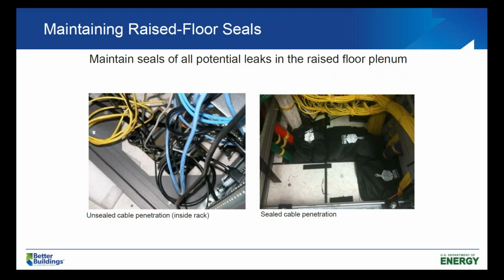Okay, so this is looking down at the floor inside a rack, and this is a common problem. Cable penetrations through the floor not being properly sealed, as on the left, and on the right, you can see the cables have been neatly bundled, and there are these black pillow-like objects that block the excess cutout area to reduce that bypass airflow problem. Next slide.